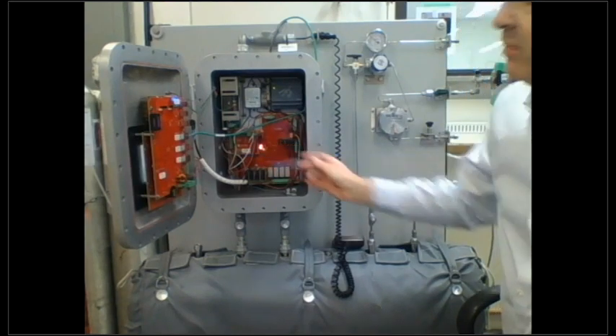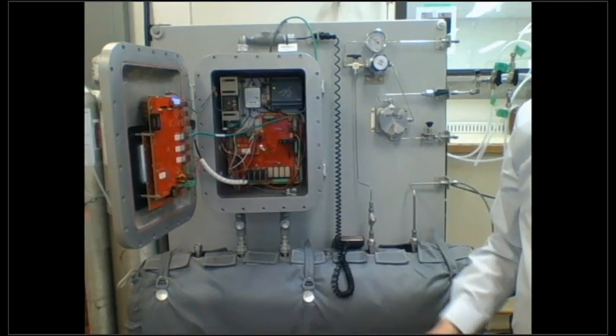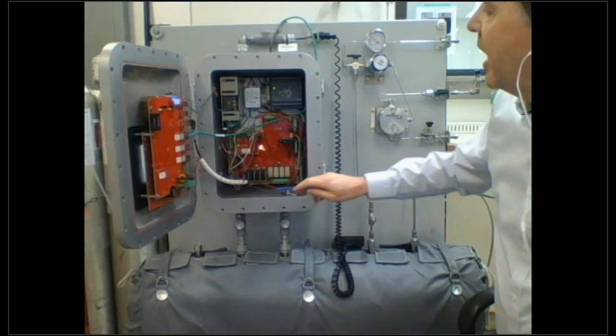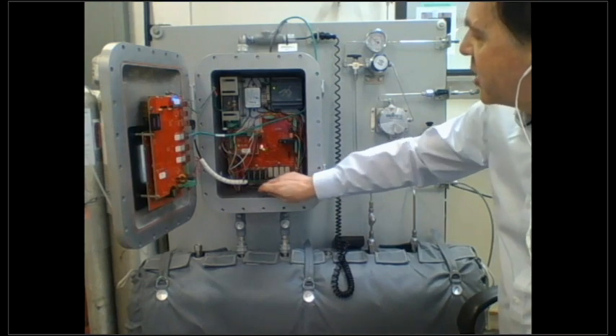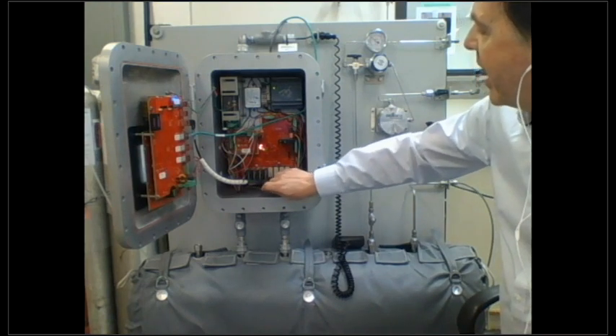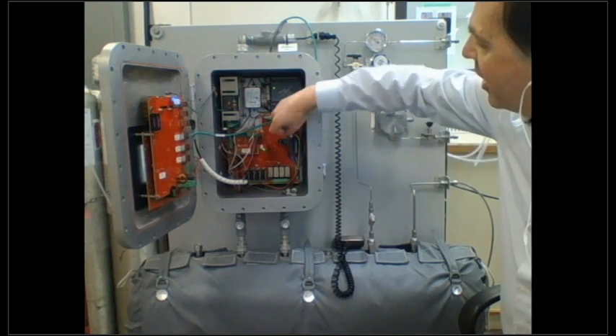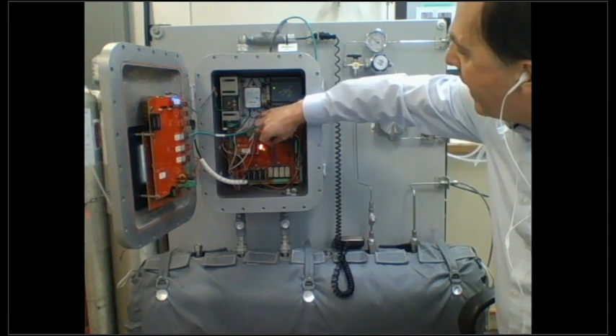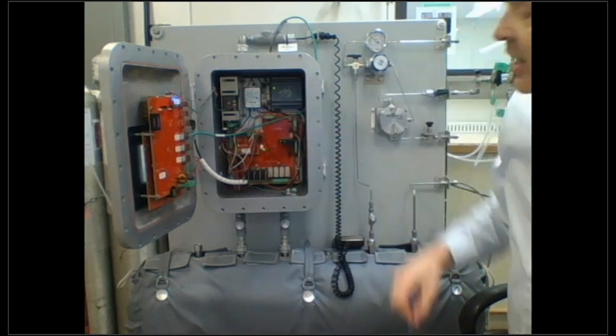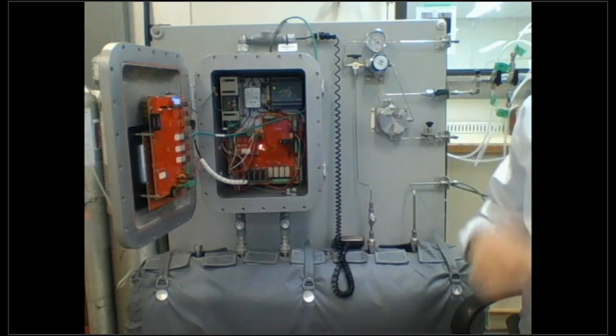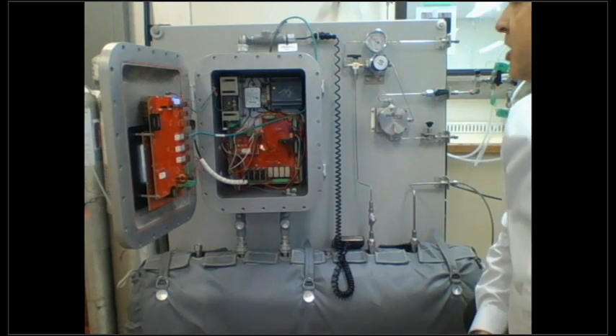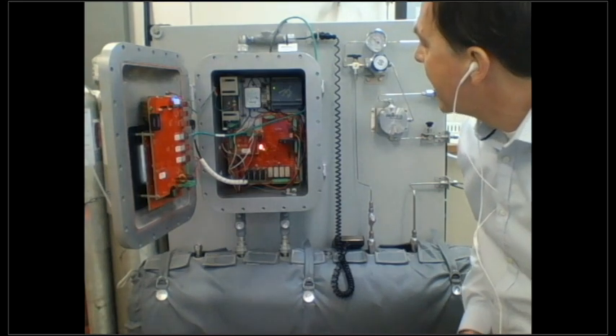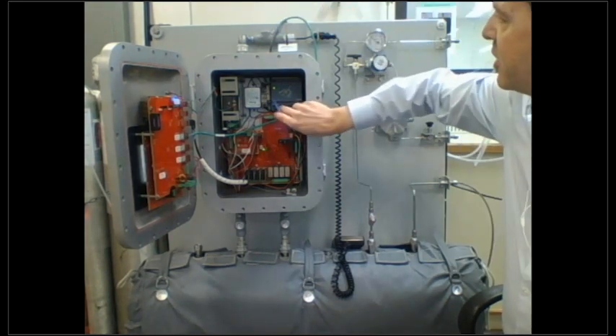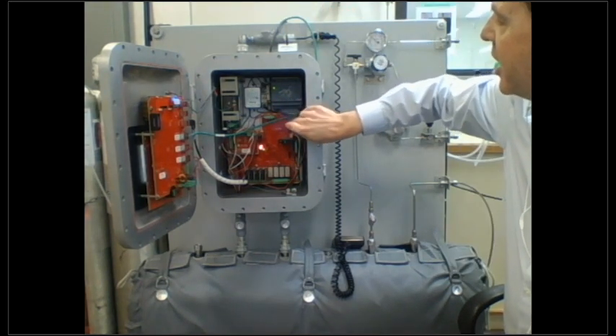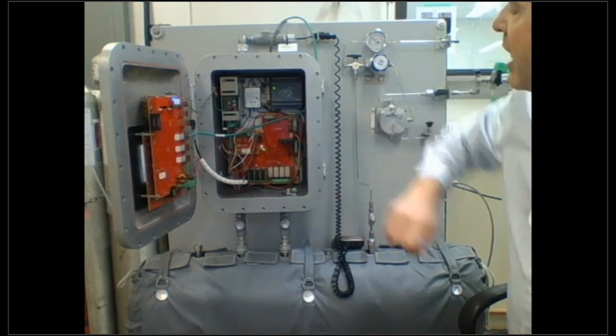There are 4 analog outputs here. There are 4 relay outputs here that are configurable for fault alarms or concentration alarms. And then we have some solenoid drivers along the side here that are used for switching solenoids for stream switching, calibrations, and things of that nature. Power comes in through the top. The power connection is right here. This is an internal power supply that provides 24 volts to the rest of the system.